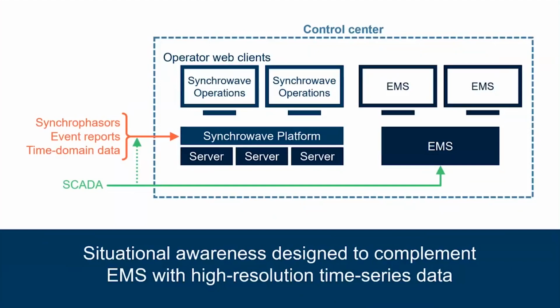Synchrowave Operations allows operators to drill into real-time data and fault information for any asset being impacted by an active fire. So basically what you do is you have eyes inside your system, so you can look at the system as a whole and get more information on what the location of the fire is and how it's impacting your system. So it gives you a picture or information at a higher resolution than previously available with SCADA and EMS systems.